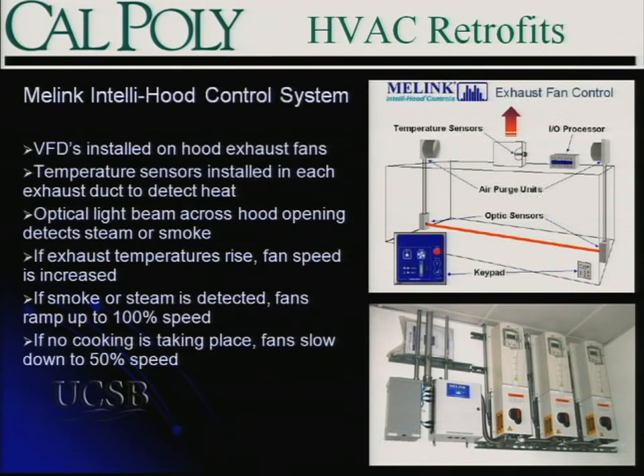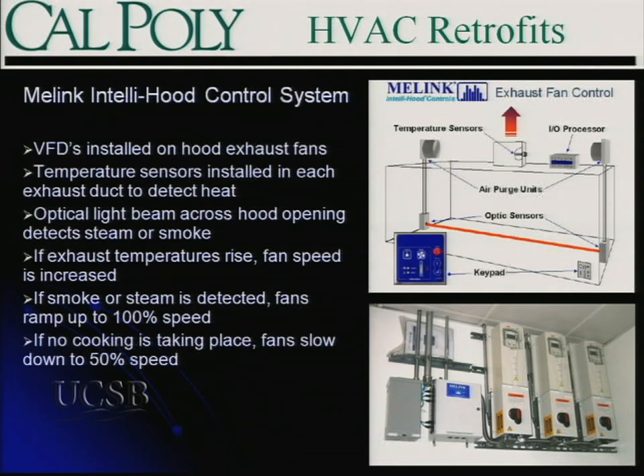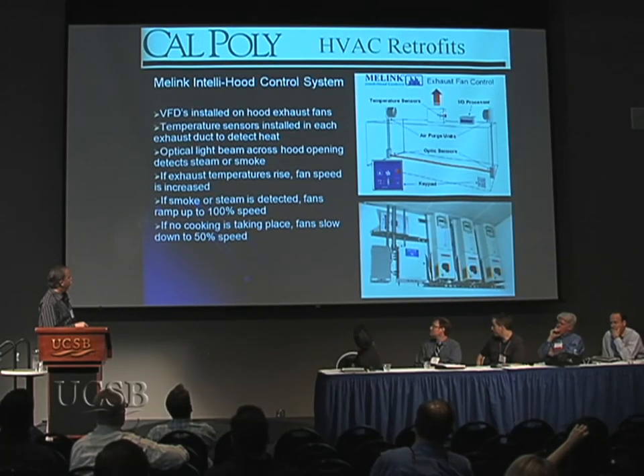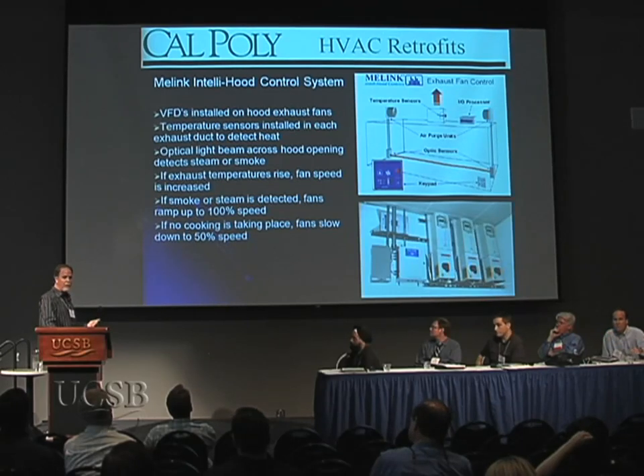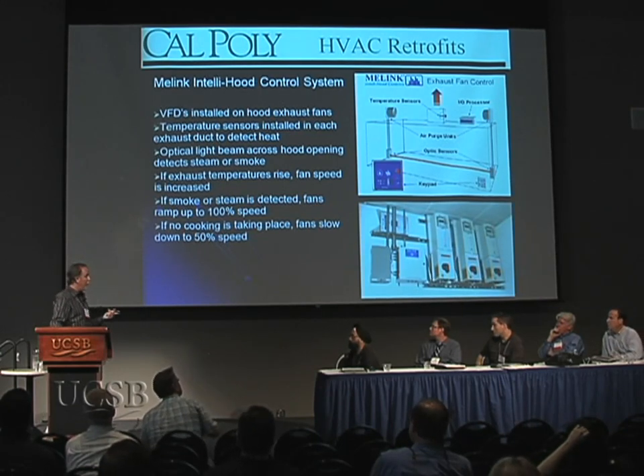The solution is to slow the fans down when they're not cooking. The Melink system is quite simple: it uses a light beam shot across transmitters mounted on the bottom of the hood. If the beam is interfered with by steam or smoke, it detects cooking activity. Additionally, a temperature sensor is located up in the exhaust duct. Monitoring those two inputs determines what the VFDs need to do. If there's no cooking — exhaust air isn't hot and you can't see smoke or steam — you run fans down to minimum speed, typically about 50%. If you detect a temperature rise, you ramp fans up to maintain a certain maximum temperature. If you see smoke or steam, they go to full speed automatically.